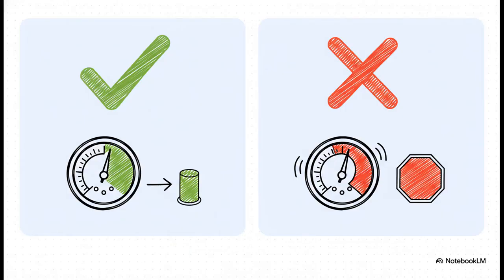So this is where we hit a fork in the road, and your pressure gauge tells you exactly which path to take. If that pressure change was less than 30 psi, the manual says your valve is good to go. Awesome. You can now move on to checking the cylinder. But if that needle jumped more than 30 psi, your diagnosis stops right here. The valve is defective and it's got to be replaced.